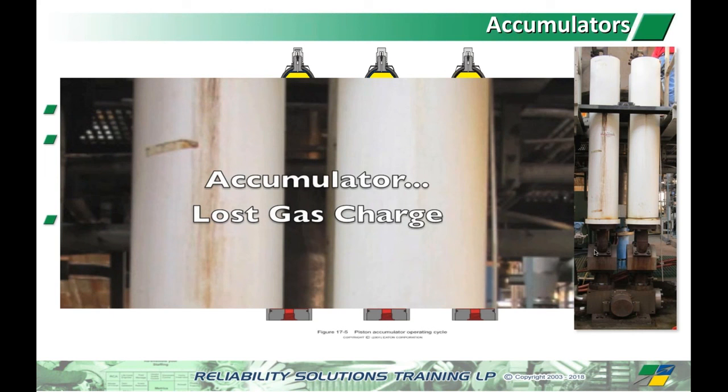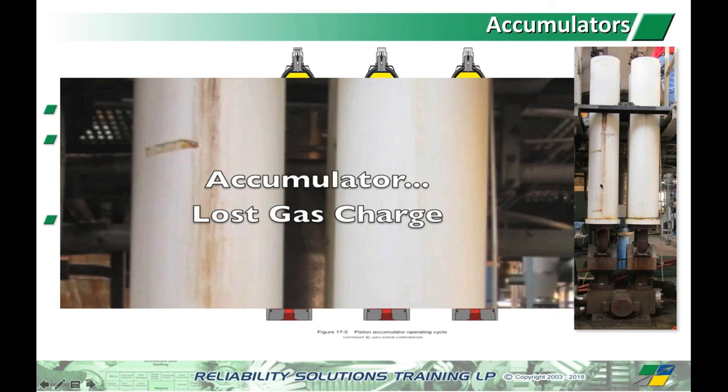knew that is it was different to the others. So in this particular rig, you've actually got 4 accumulators, and these were on a system that was running a pressure diffuser at a pulp mill. They have hydraulic pumps that pump these things up, and then when they want this diffuser to move quickly, they discharge these accumulators. So they have that cycle that you could hear. And they'd been having trouble. The diffuser wasn't moving the right way, and we went around and started trying to help troubleshoot them.